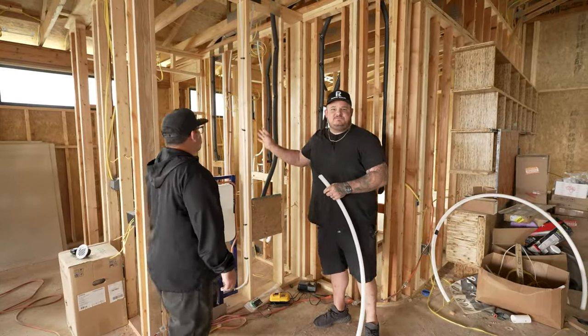At our top plate we put nail plates so that when we're drywalling or putting in cladding we don't come through and hit this pipe with a screw. Above us we have PVC drain lines hanging by metal perforated strips — that's called strap iron. We use strap iron to support our plumbing and maintain a constant fall. Fall is important because our sewer system works off gravity — we need at least a quarter inch per foot on fall on horizontal pipe so the drain flows correctly and solids go down.